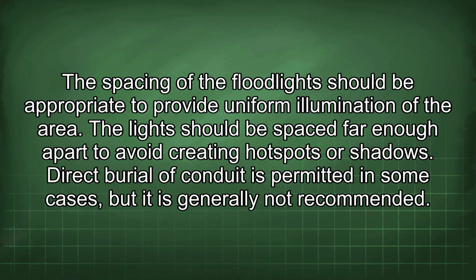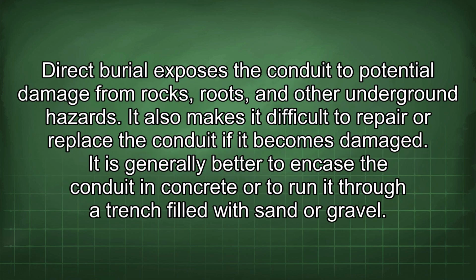Direct burial of conduit is permitted in some cases, but it is generally not recommended. Direct burial exposes the conduit to potential damage from rocks, roots, and other underground hazards. It also makes it difficult to repair or replace the conduit if it becomes damaged. It is generally better to encase the conduit in concrete or to run it through a trench filled with sand or gravel.